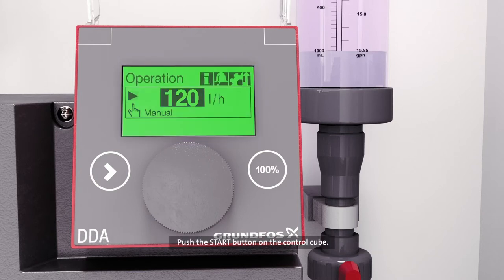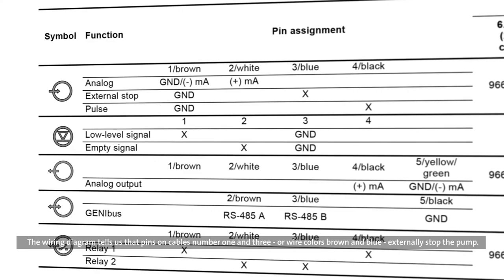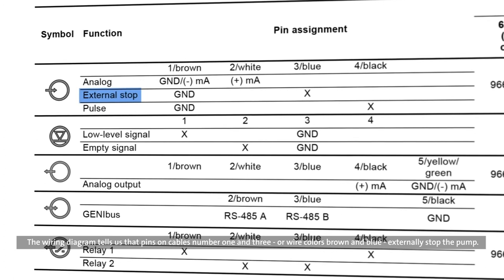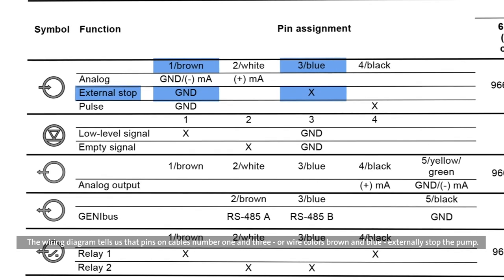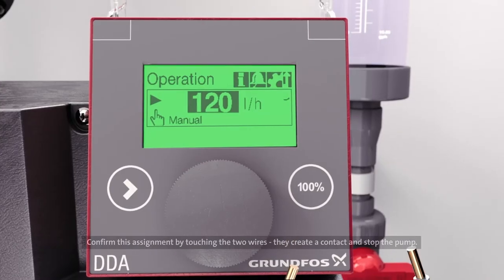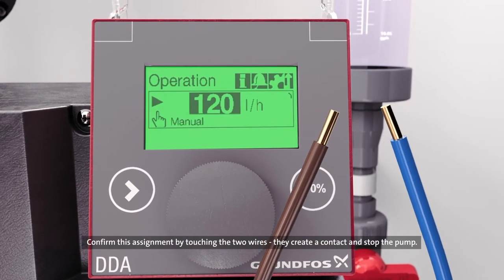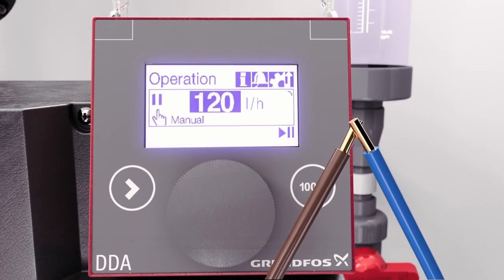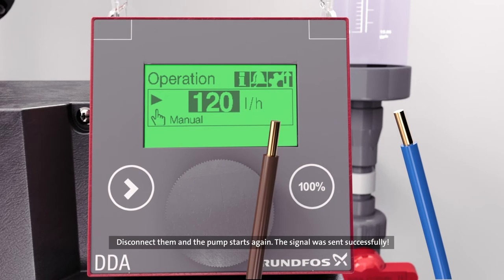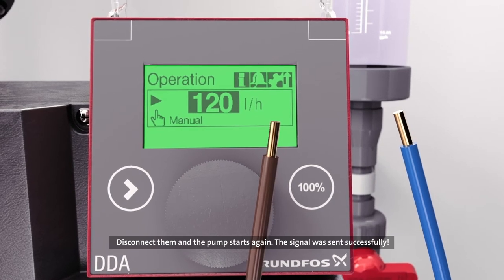Push the start button on the control cube. To send a remote stop start signal, we use a dry contact. No voltage needed. The wiring diagram tells us that pins on cables number 1 and 3, or wire colors brown and blue, externally stop the pump. Confirm this assignment by touching the two wires. They create contact and stop the pump. Disconnect them and the pump starts again. The signal was sent successfully.